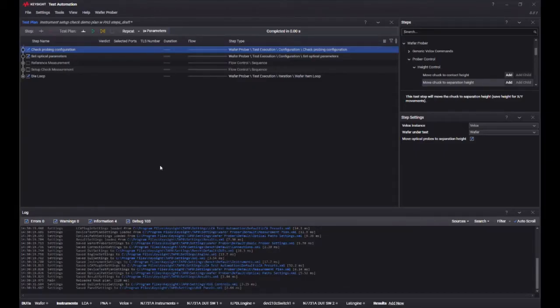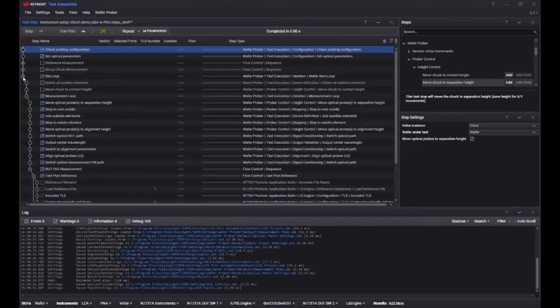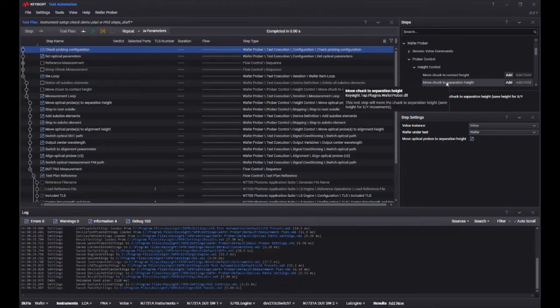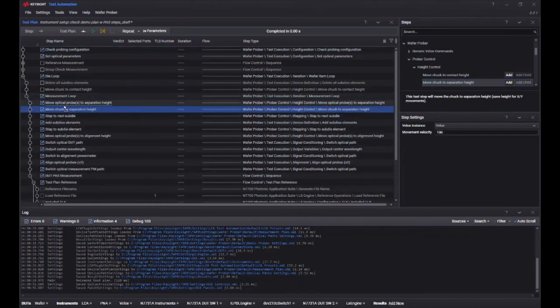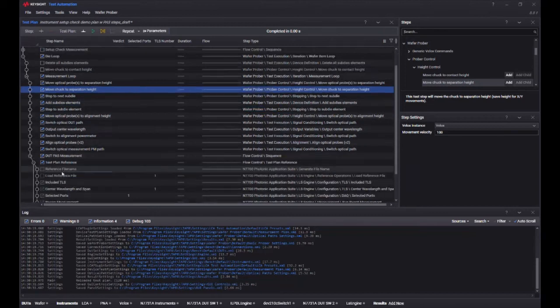In the test automation platform, you can easily configure a measurement scenario on wafer. Here in this view, we have a die view or die loop where you step on the wafer from die to die and you see the measurement loop. You can actually easily move or add functions that realize the communication with the wafer prober, like you just move the probe to separation height or the chuck to separation height.